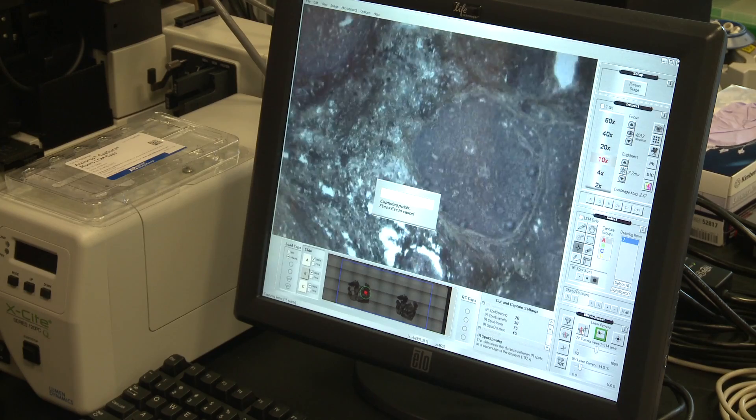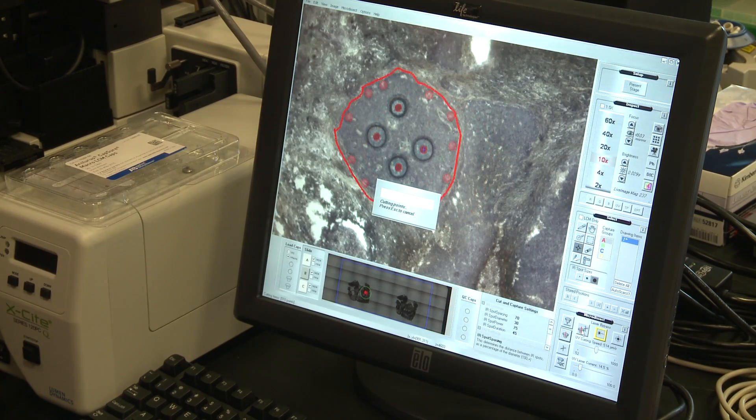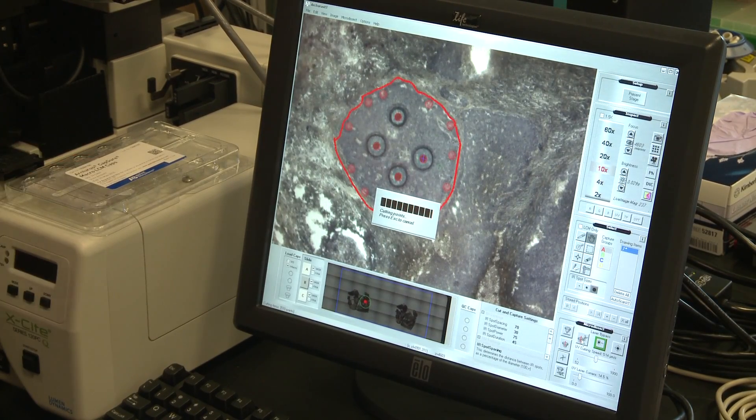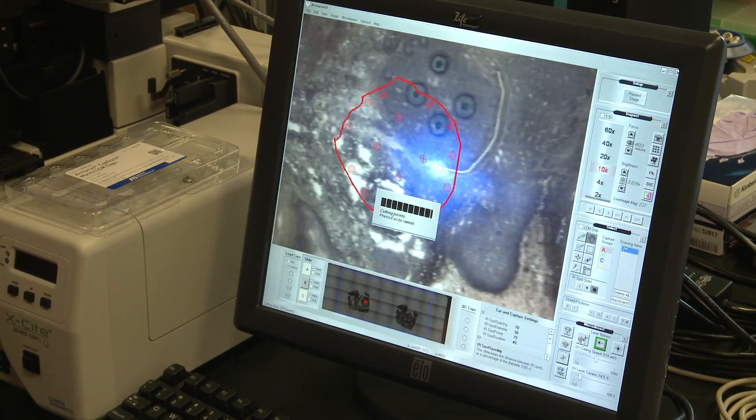The Arcturus system allows you to use the infrared for small numbers of cells, or use the infrared capture method to hold on to the center area of a larger piece of tissue that's been cut out with the UV laser. The XT is really the best instrument compared to competitors because you can do both UV cutting and infrared capture. You hold on to your sample with the cap and retain the orientation of all the cells — an advantage over systems where you cut something and drop it into a tube or catapult it, losing orientation.